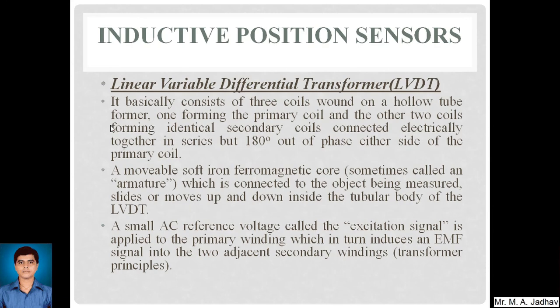The next type is inductive position sensors. We will go through the Linear Variable Differential Transformer, shortly called the LVDT. It basically consists of three coils wound on a hollow tube — one forming a primary coil and the other two forming identical secondary coils connected electrically in series but 180 degrees out of phase, on either side of the primary coil. A movable soft iron ferromagnetic core, sometimes called an armature, is connected to the object being measured and slides up and down inside the tubular body of the LVDT. A small AC reference voltage called the excitation signal is applied to the primary winding, which in turn induces an EMF signal into the two adjacent secondary windings.